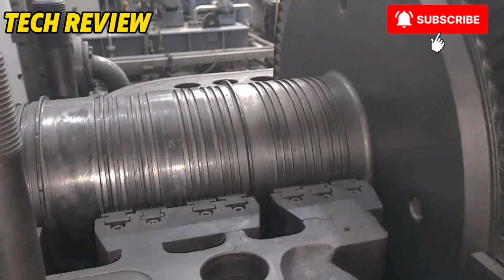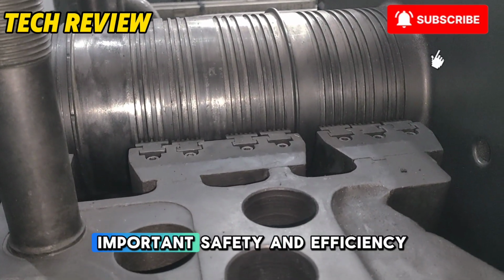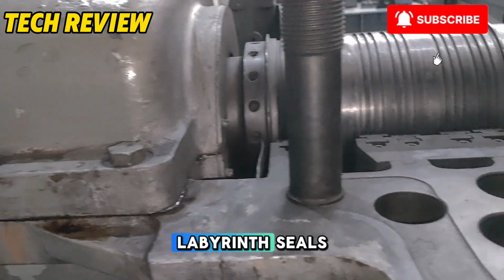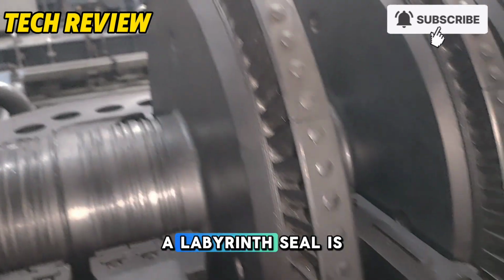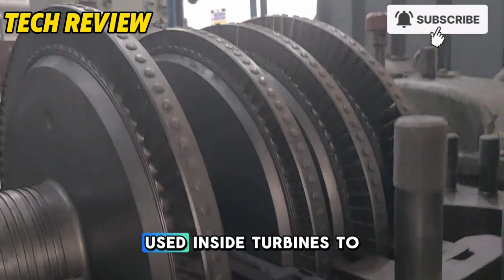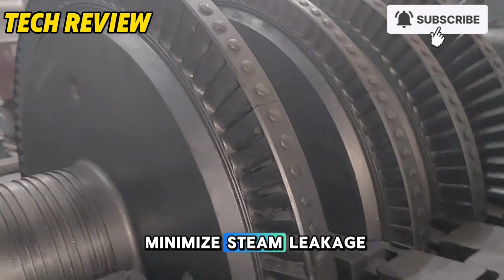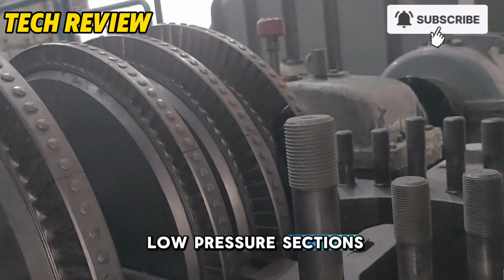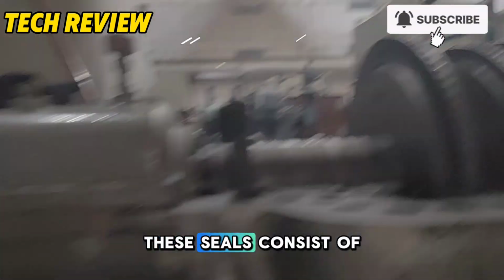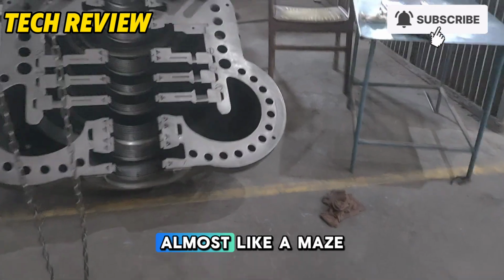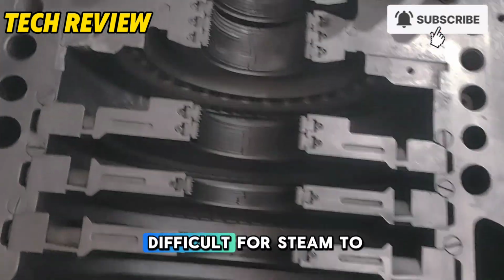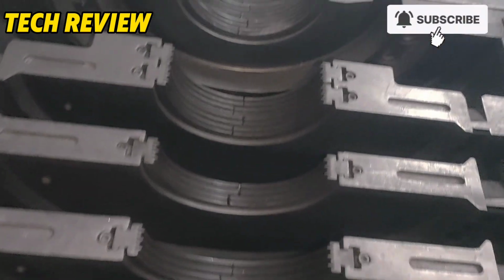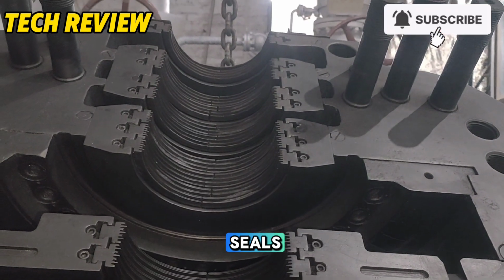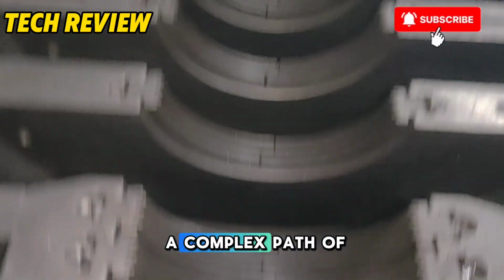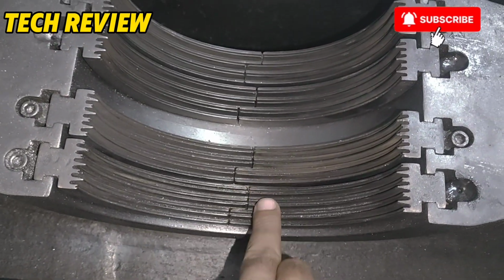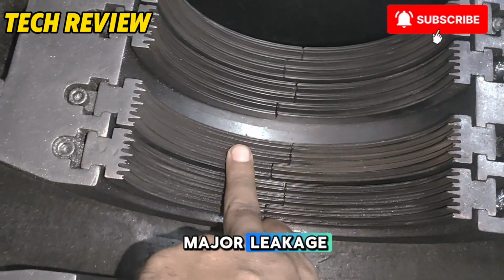5. Labyrinth seals. Now let's talk about an important safety and efficiency feature, labyrinth seals. A labyrinth seal is a special type of seal used inside turbines to minimize steam leakage between high-pressure and low-pressure sections. These seals consist of a series of ridges, almost like a maze, which make it very difficult for steam to pass through. They are called labyrinth seals because steam has to pass through a complex path of chambers and restrictions, losing energy and preventing major leakage.